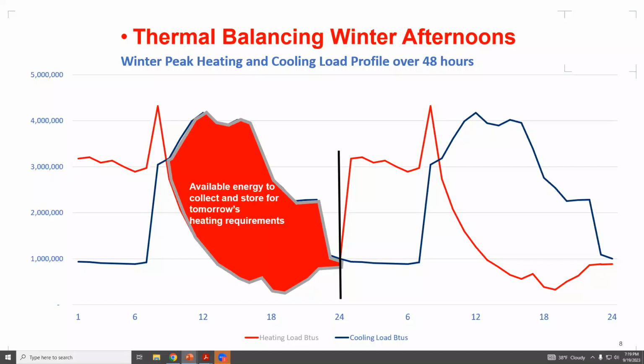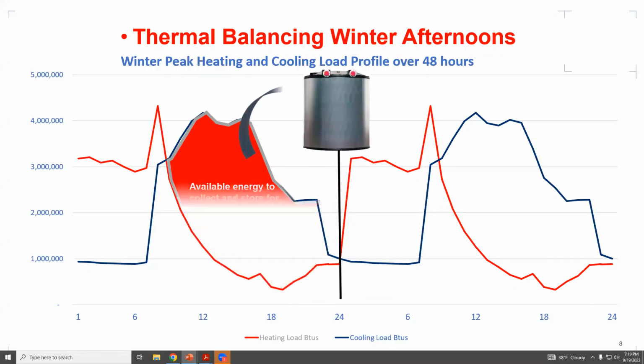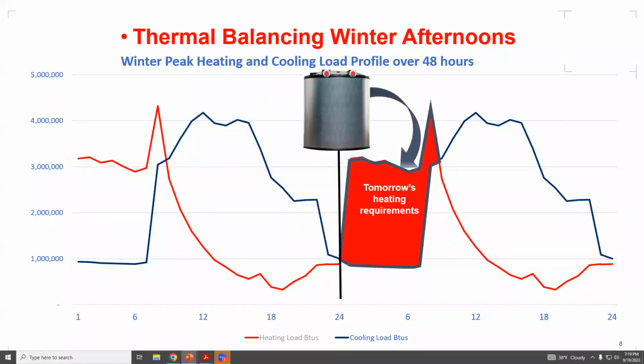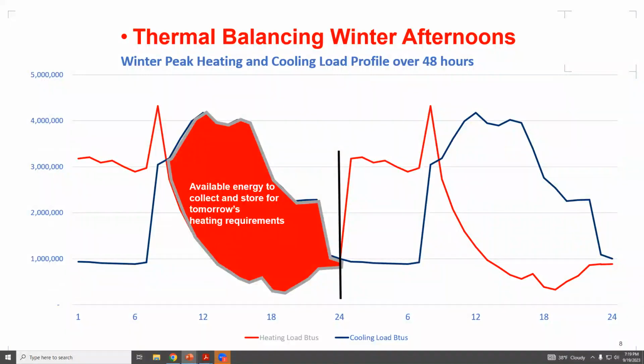You can see the peaks for heating and the peaks for cooling. On the left, underneath the shaded area under our cooling load, we have a cooling load, meaning we have the ability to pull heat from our building. This is available energy to store into our thermal tanks, storing it by melting any ice in those tanks. That then allows us, when we have a heating load, to pull that stored energy out via water and use it for heating. It just flips back and forth.